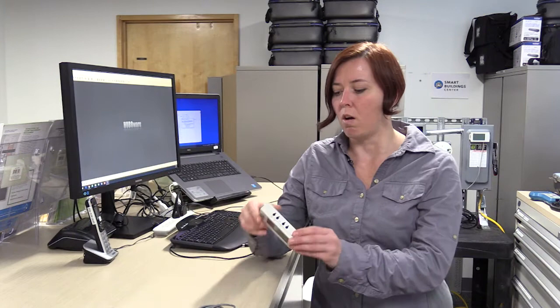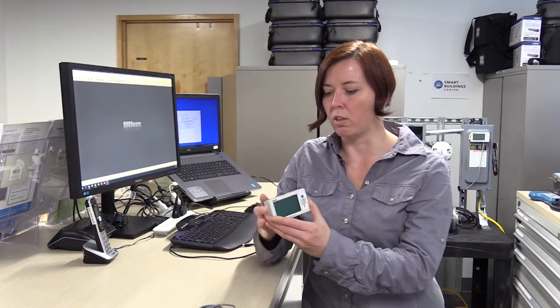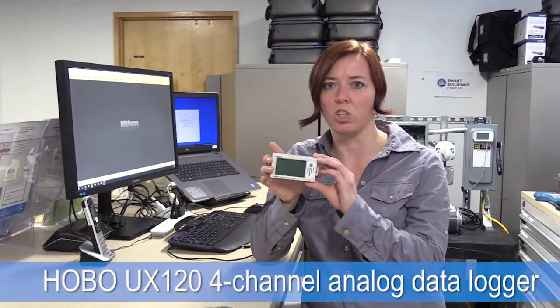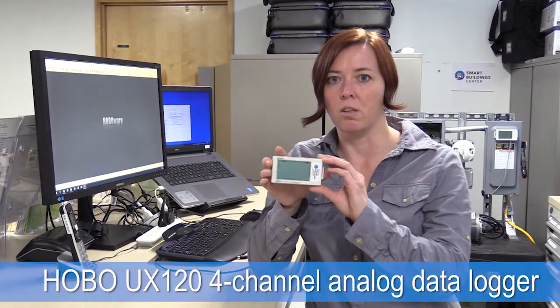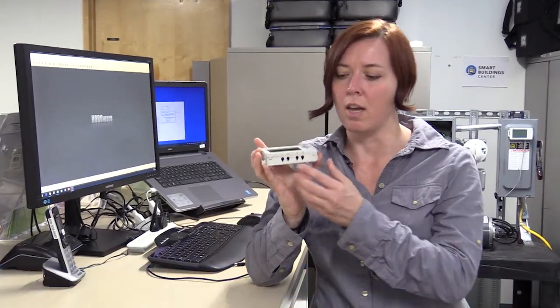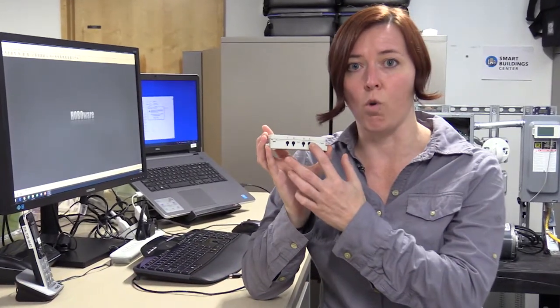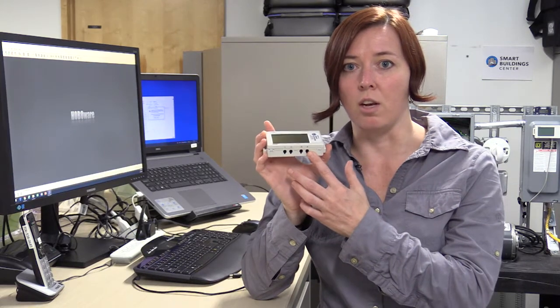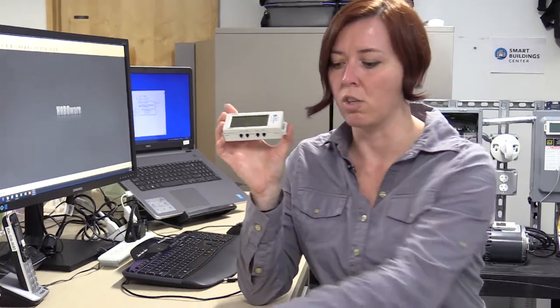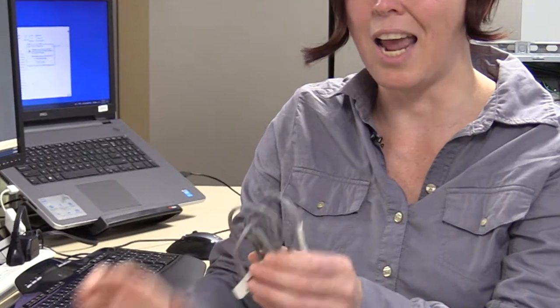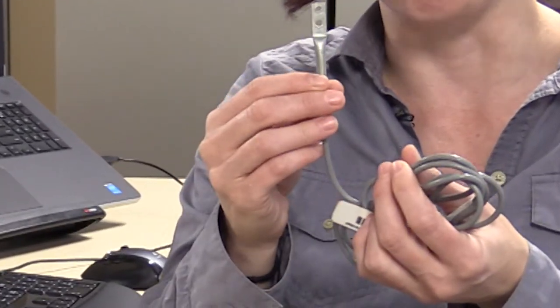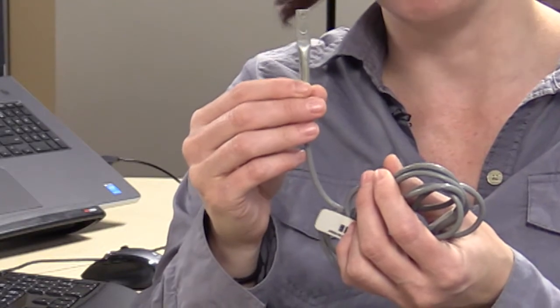First we'll configure the loggers, and the loggers we'll be using today for this demo are Hobo loggers. This is the UX120 four-channel analog data logger. This is a very versatile logger. It has these four ports for an external sensor, and you can use various types of sensors. The one we'll be using today is a flat plate sensor for measuring the hot water supply pipe from your boiler.